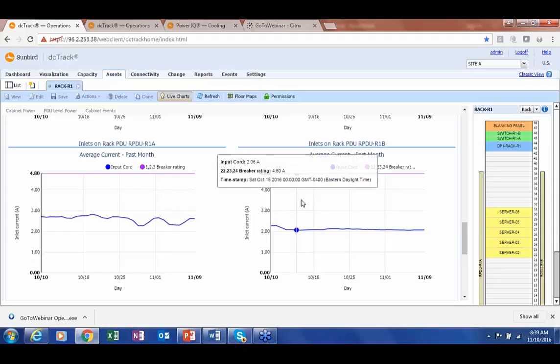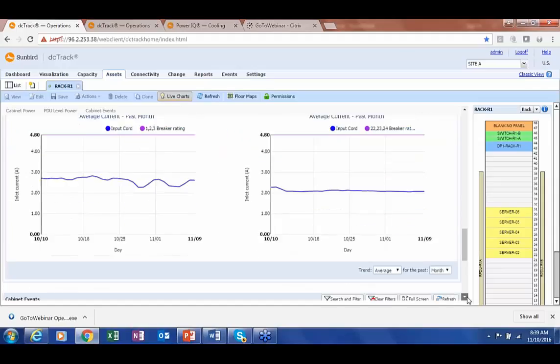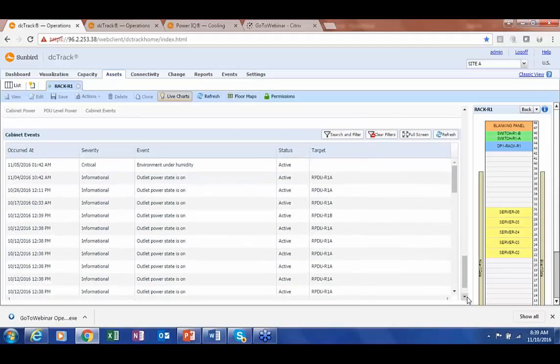So in both cases, I have a lot of capacity within this cabinet, which is good, consistent with the higher level view, but now I'm seeing it on a PDU by PDU basis. I see the events here, and clearly humidity is too low, but I can also see what changes have gone on recently. Seems like outlets have been turned on, so maybe this increased load has caused the fans to move more quickly and the cooling systems to operate harder, which may have removed some moisture from the air, and I might have to address that.